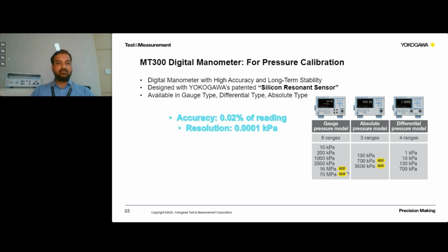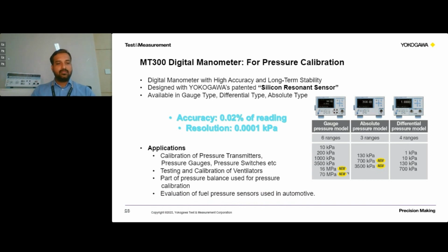best possible resolution available. So from an application perspective, these instruments can be used for calibration of transmitters, pressure gauges, pressure switches, and testing and calibration of ventilators. This is one of the prime applications which we are discussing now. When we talk about ventilators, ventilators will be dealing with a very minimum pressure. Ventilators are for checking the air pressure of the lungs or the air pressure of human respiration. Very minimum pressure will be involved, so it is very critical and important to measure the available pressure there and how effectively those pressures are measured. For those kinds of applications, these products are very useful.